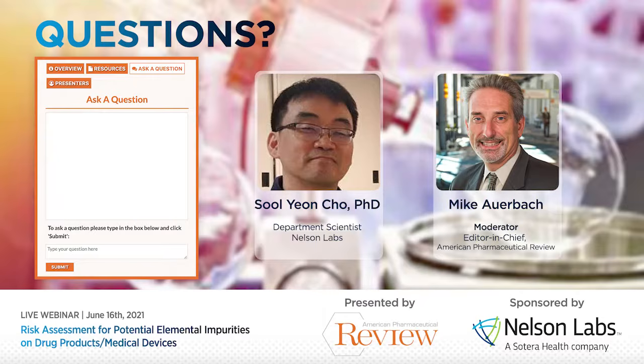Depending on the sample formulation, if it's very simple, it could be a very simple verification regarding the sample, applying the logic and the manner presented here. But if a sample is complicated, for example a powder that is very hard to dissolve, then we need to go through the sample prep process and validate that sample preparation method, to see whether it is appropriate for the specific sample. I should say this includes heating or acid digestion. Nowadays we use microwave acid digestion. So the answer could be yes and no, depending on the sample formulation.